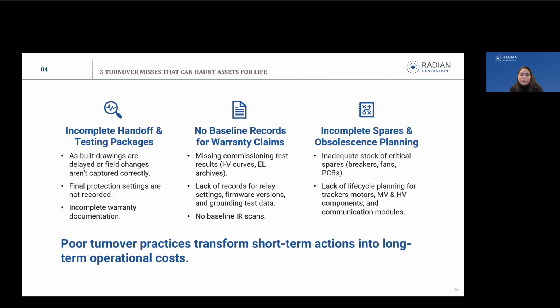The lack of planning for things we know are common failure points, like tracker motors, some medium voltage components, communication modules, not having a plan for replacing those. Having a reactive approach to spare parts, if driven by a lack of initial planning, inevitably leads to extended downtime and revenue loss when critical or even non-critical components fail.